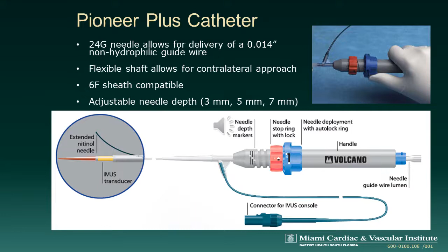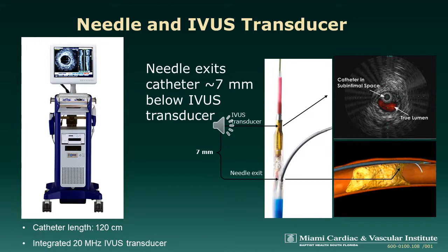The needle and the IVUS transducer are shown on this slide here. And the needle exits the catheter approximately 7 millimeters below the intravascular ultrasound transducer. So that's an important thing to know. The catheter length is 120 centimeters, and there's an integrated 20 megahertz IVUS transducer incorporated into the device.